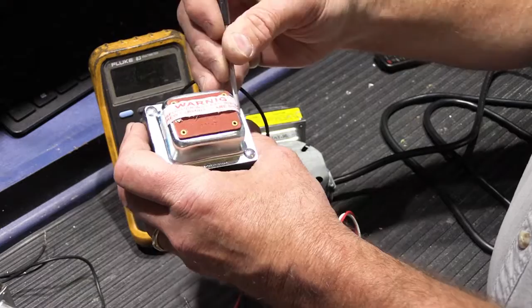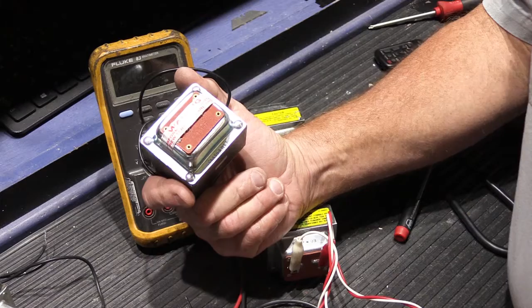So there's your warning, don't short the screw terminals. We learned early on when we would install these, when the 4406s were new, to make sure the circuit breaker was turned off when we made the red and white wire connections on the screw terminals, because one little slip and you'd blow the fuse and be out of a transformer, and then you'd have to go back to the shop because you didn't have one with you. It was a giant pain in the neck, so you learn pretty quickly.